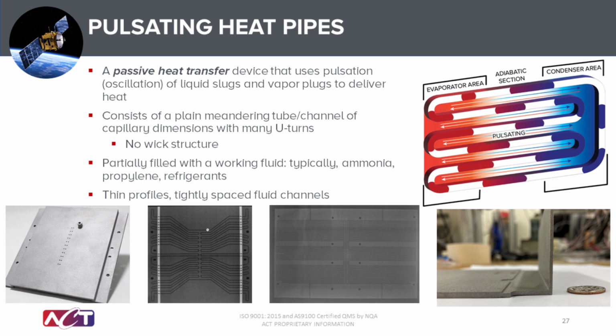So one way to get around the freezing then is the development of pulsating heat pipes. So with pulsating heat pipes, we can do smaller geometry. We can have a heat pipe on this board level, but we can actually use ammonia, propylene, refrigerants, other working fluids that don't freeze where water freezes. So that's one benefit of the pulsating heat pipe.